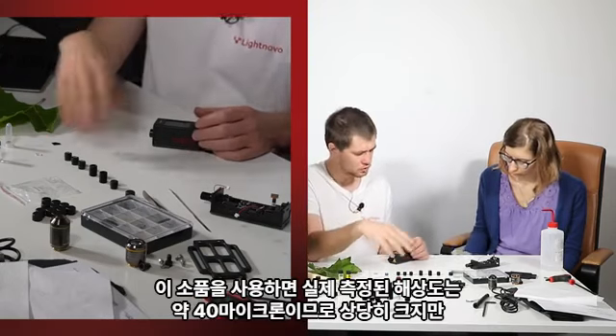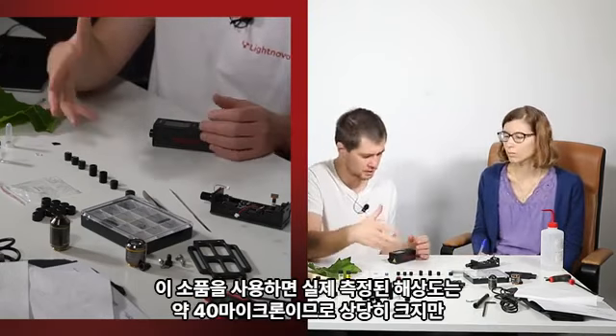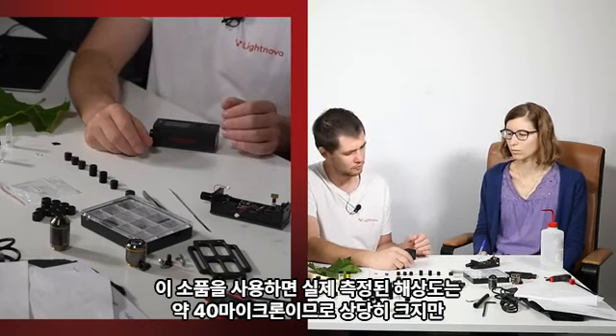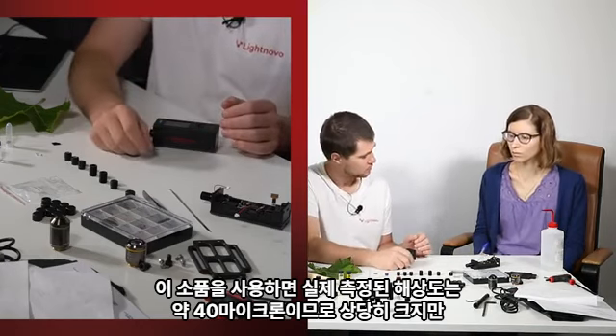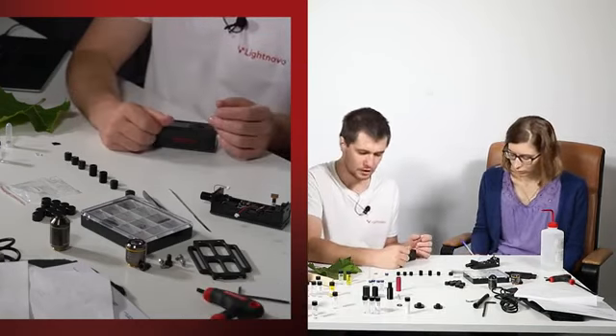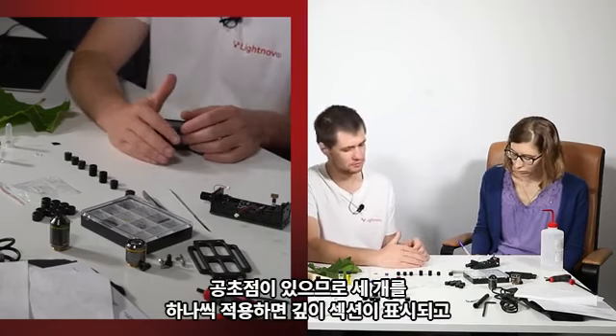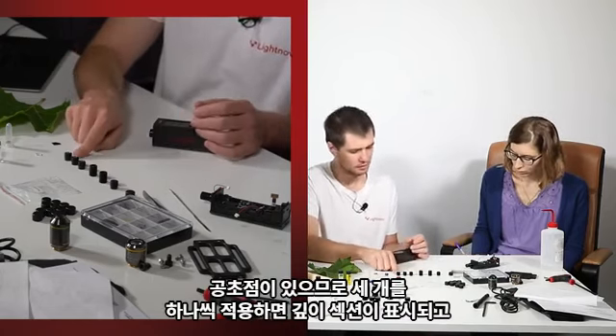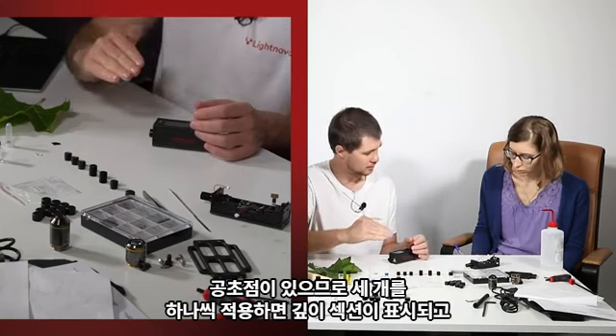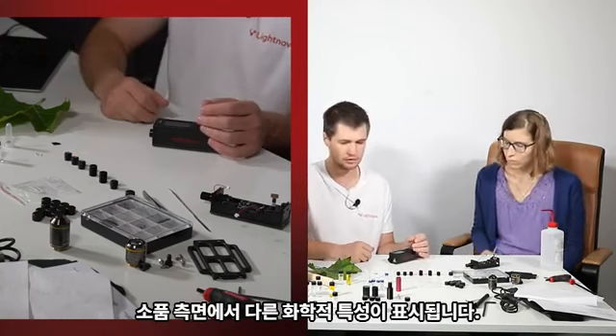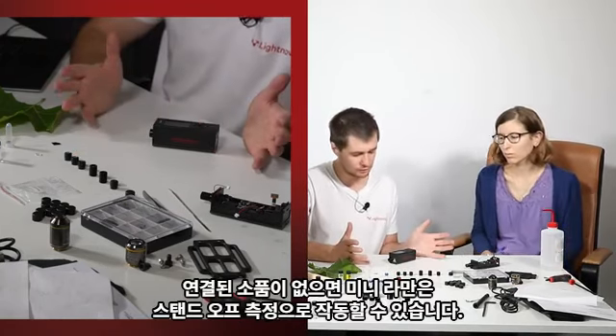The depth resolution with these probes, actual measured resolution, would be approximately 40 microns. So it's quite large. However, there is a confocality, so if you apply the three of them one by one, you will see depth sectioning and you will see different chemical signatures. In terms of probes, that's it.